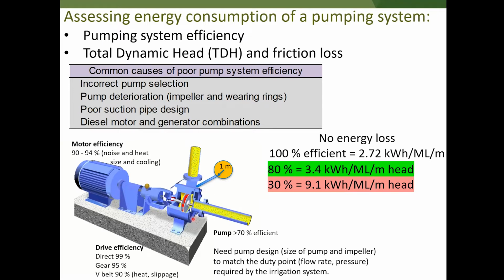For older systems, we get pump deterioration, so impellers deteriorating or the wearing rings deteriorating, and that'll reduce the efficiency and might require an overhaul of the pump. The suction line also has a big impact on the efficiency of the pump. So if there's any restrictions to water getting into that pump or turbulence of the water going into the pump, then that'll cause inefficiency. We've had one example where there was a sudden contraction, so the pipe size reduced in size just before the pump, and that was probably causing a 10% reduction in efficiency because of a bit of poor design there. So we're still working to try and quantify that and check that we can improve that system.